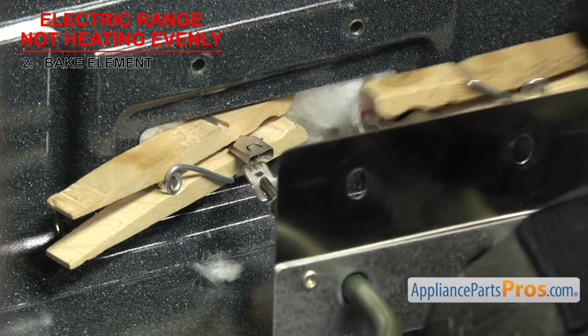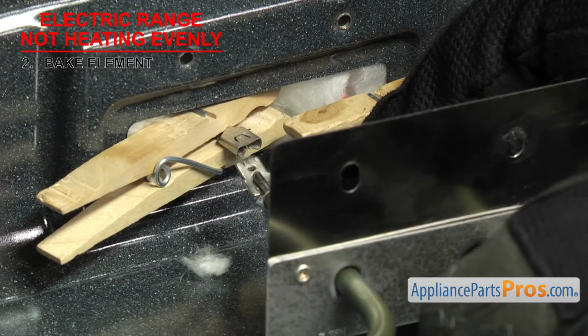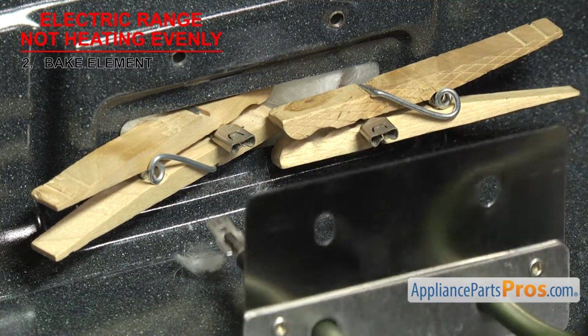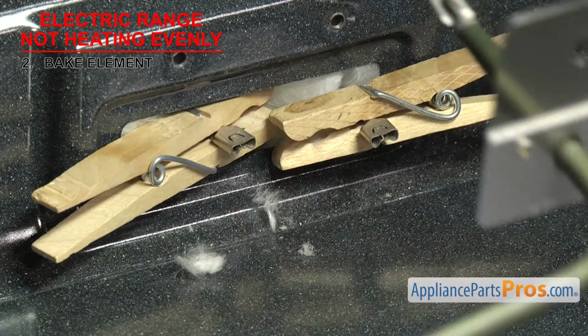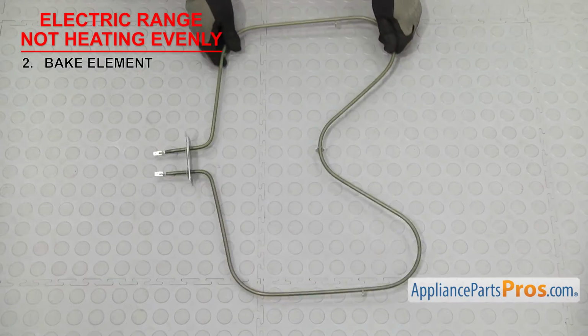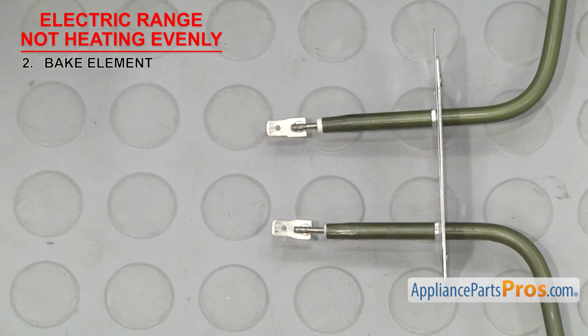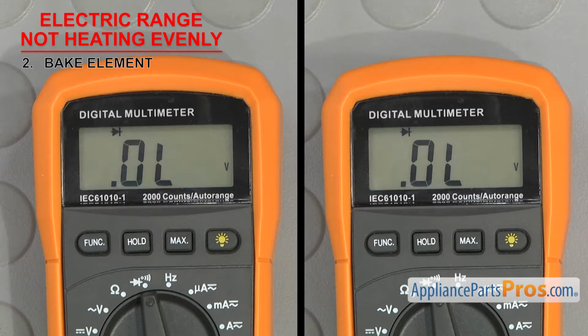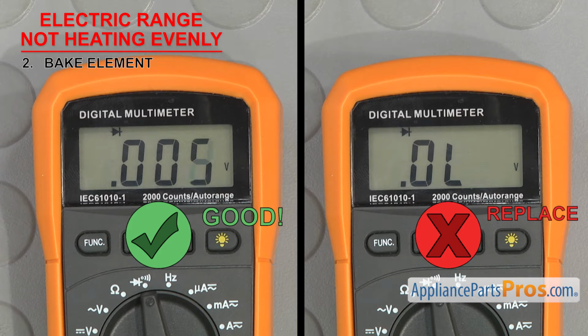Once you have access to the wires, remove them, but be careful they don't slip back through the hole, otherwise you'll have to fish them out. Then touch a test probe to each terminal of the element. If it doesn't have continuity, it's bad and will have to be replaced. Also, if you notice any swelling or damage, you should replace it even if it has continuity.